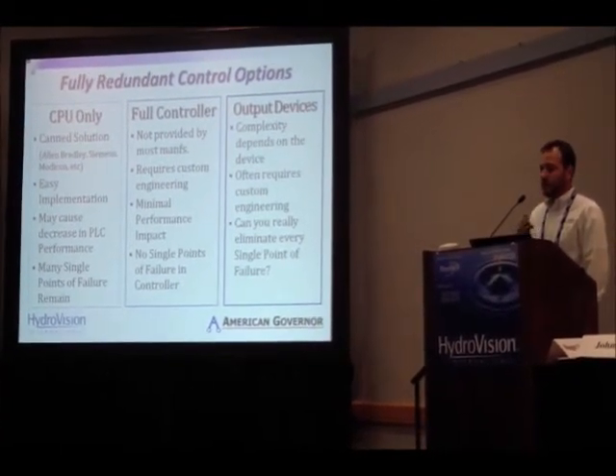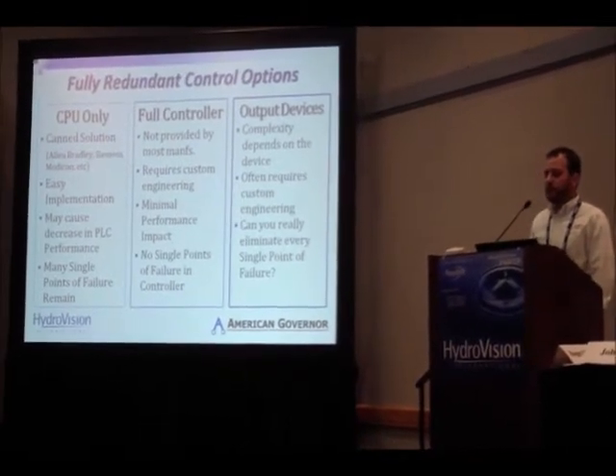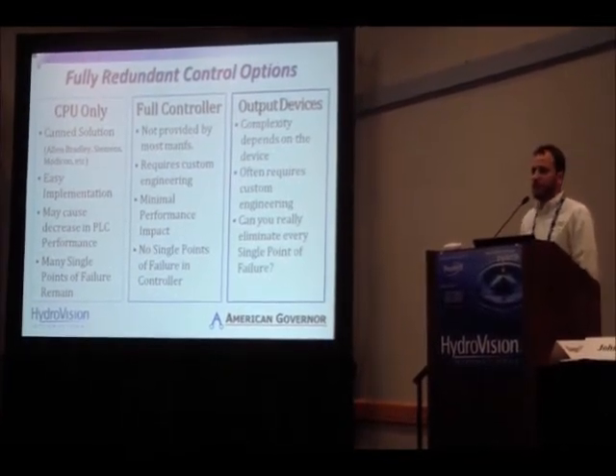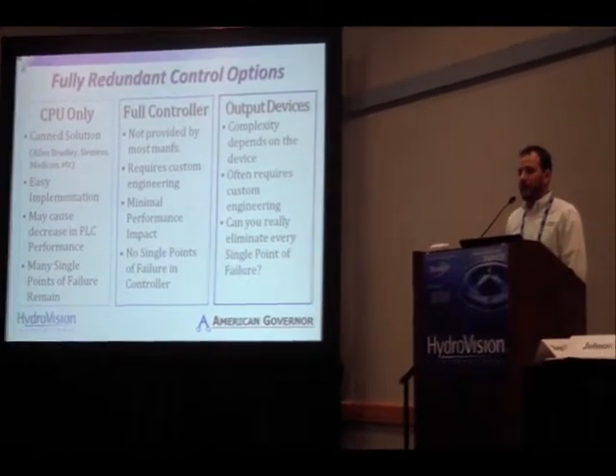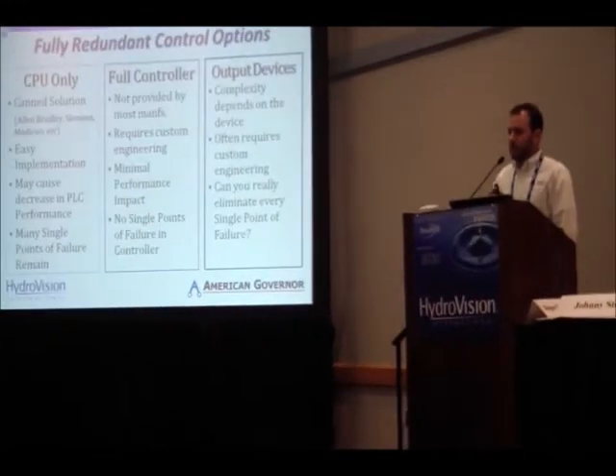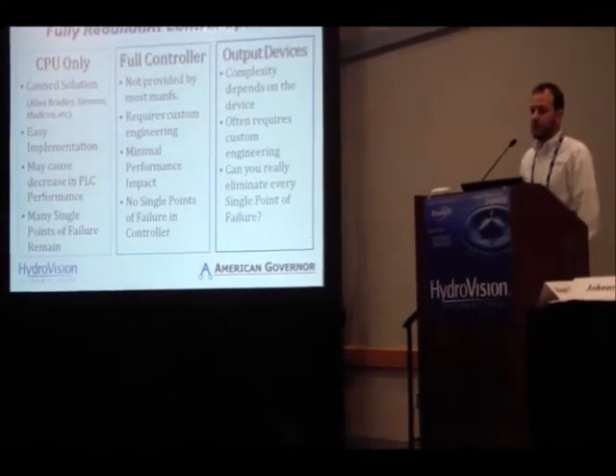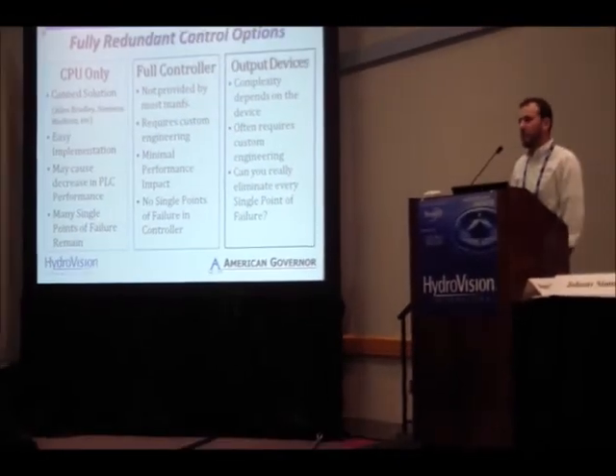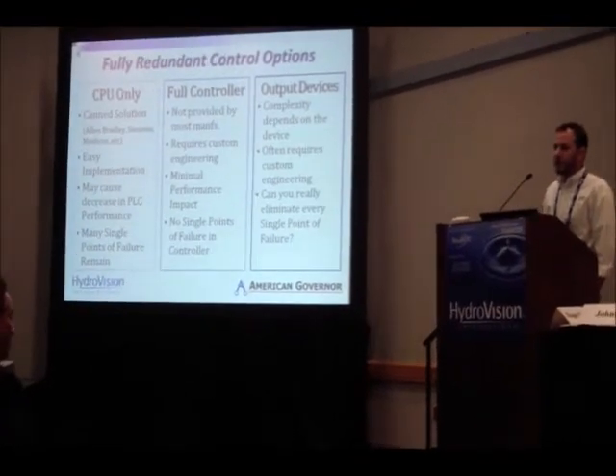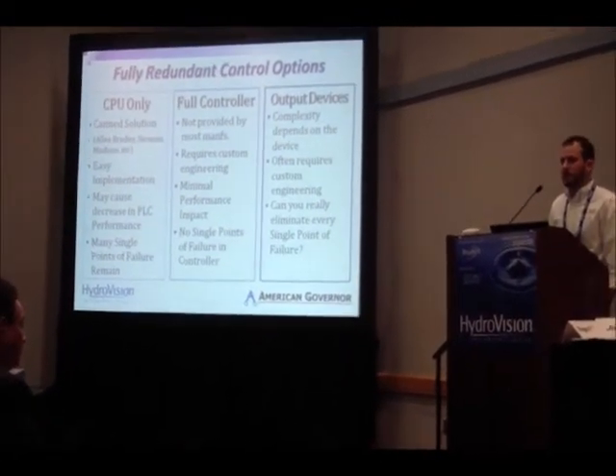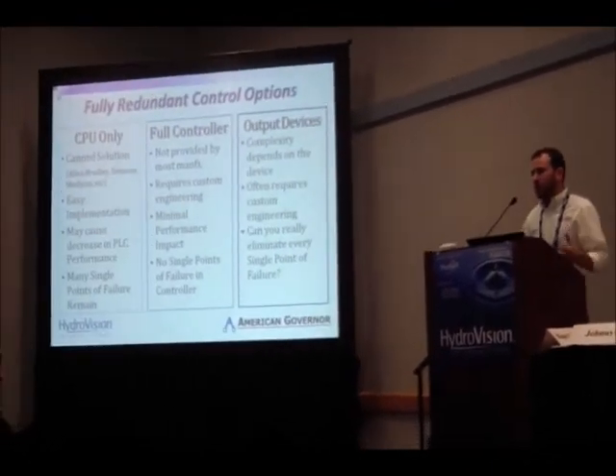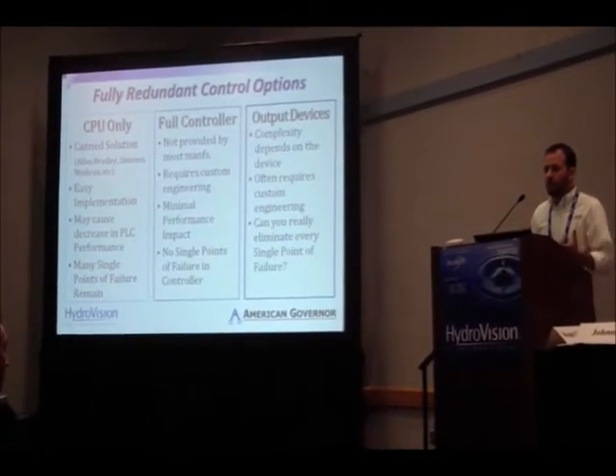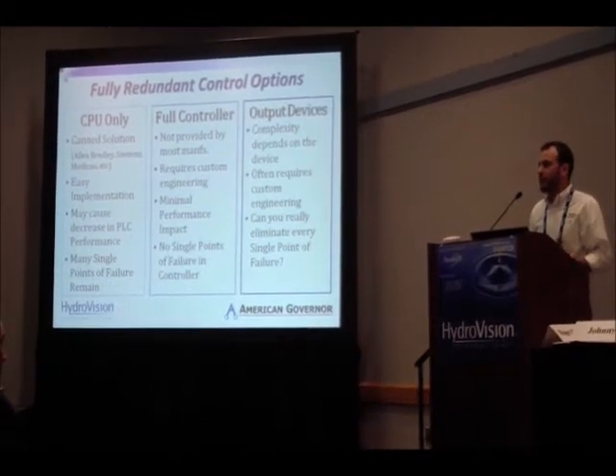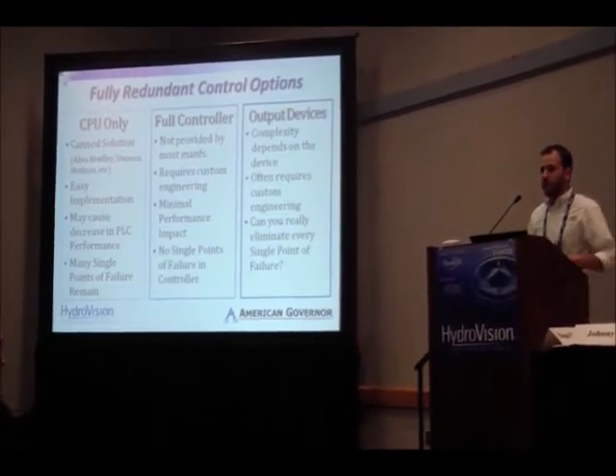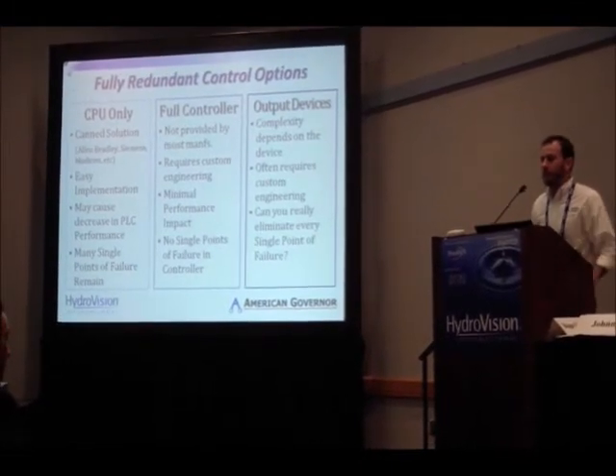So the next step would be, let's have redundant I/O across the board. And usually you'll see this in 2 fully redundant controllers running the exact same set of hardware, running parallel programs that are operating in sync. Now these often do require custom engineering. But because of that, they can be optimized and configured for your arrangement. So your performance impact is minimal. It's going to be seamless to your normal operation. And in your controller, you'll now have no single point of failure. Any controller component can fail and the unit will keep running. You'll lose some robustness because you're under your backup, but you can now take an outage at your convenience.